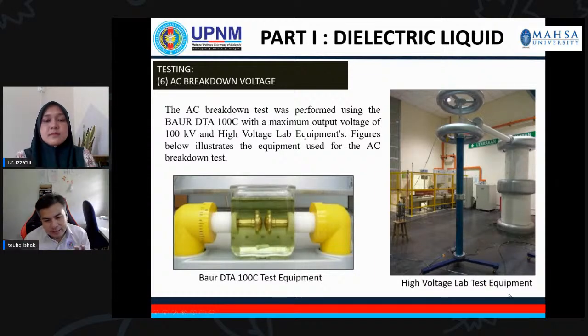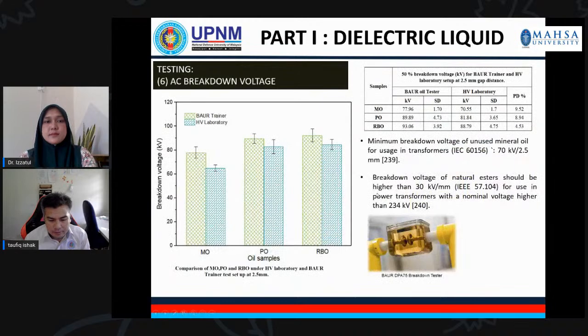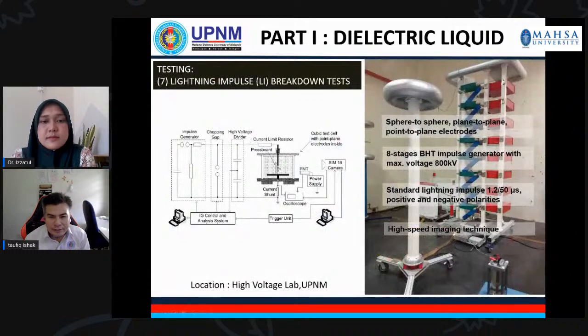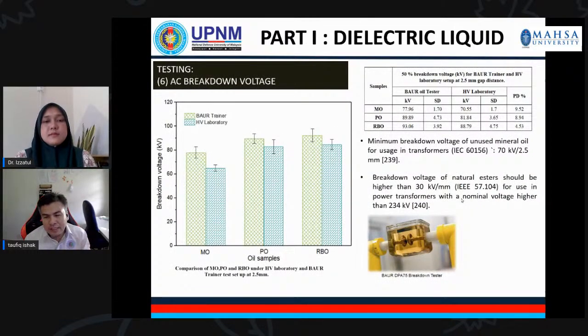So normally for this kind of testing, we will do almost 50 readings of the breakdown for each sample. Based on the study that we did, we have two kinds of sets. One is using the automatic bulk oil tester, and we also use the high voltage lab setting in UPNM, and then we come up with the average voltage for that particular testing. What we can see here is that the minimum breakdown voltage of unused mineral oil, which is new oil for the transformer, based on IEC 60156, is 70 kV per 2.5 millimeter gap that you apply for the electrode.